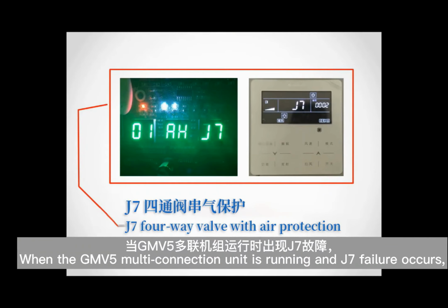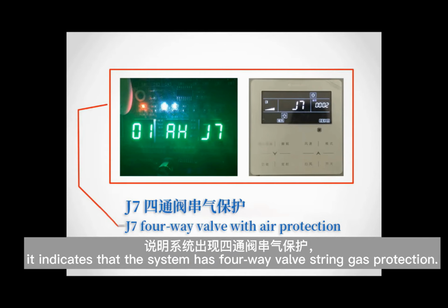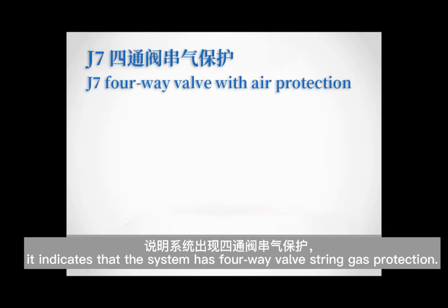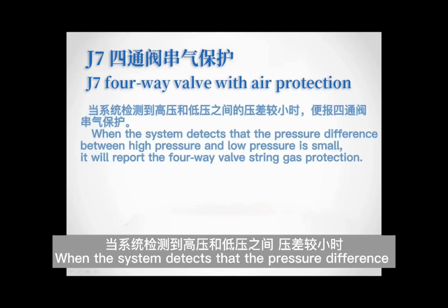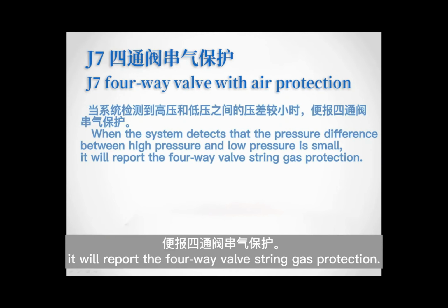When the GMV5 multi-connection unit is running and a J7 failure occurs, it indicates that the system has four-way valve string gas protection. When the system detects that the pressure difference between high pressure and low pressure is small, it will report the four-way valve string gas protection.